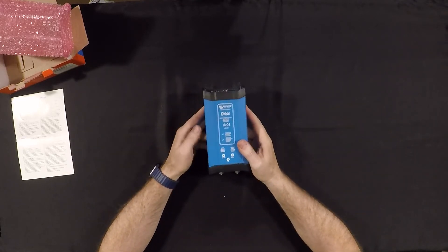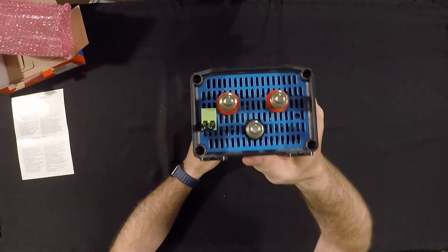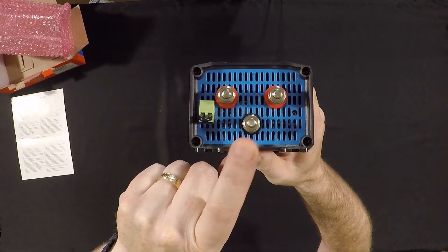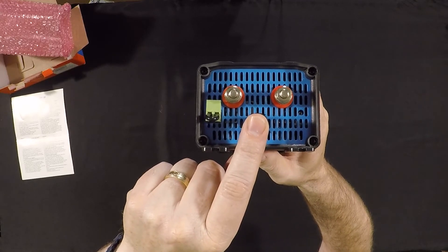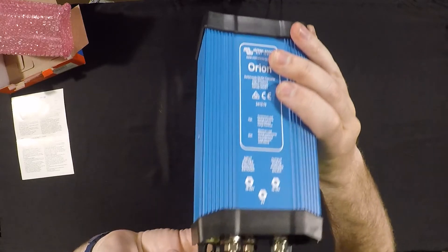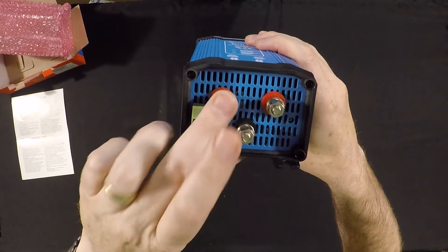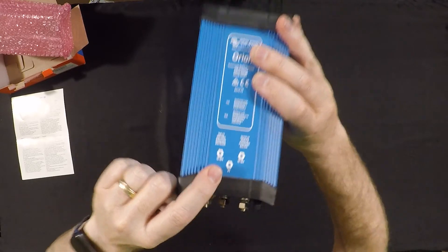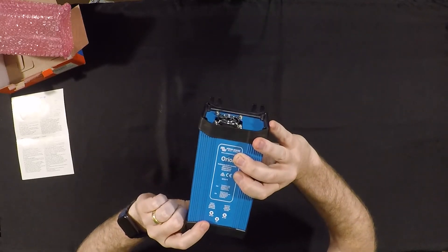And if you look at the actual connections here, you have three connections. You have a common ground that is common between both your 12 and your 24 volt side. And then you have on this side right here, this one is the 24 volt side because it tells you the numbers there. You have a range of input of anywhere from 18 to 32 volts.